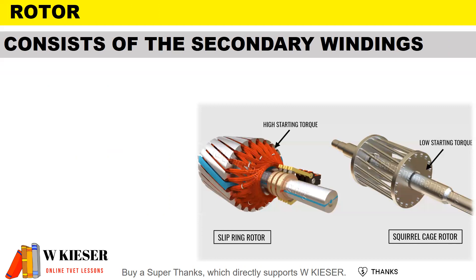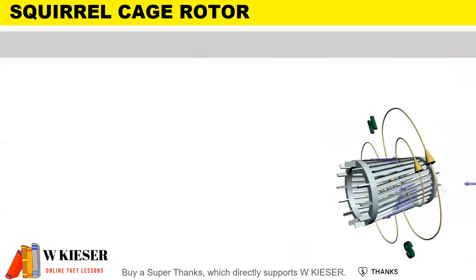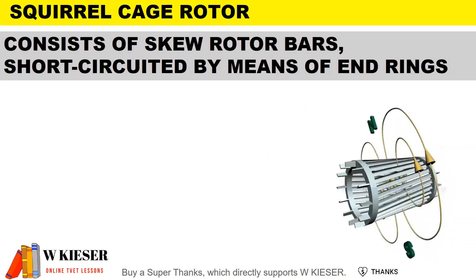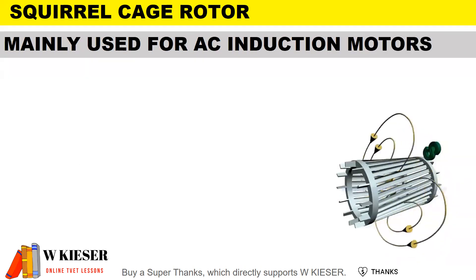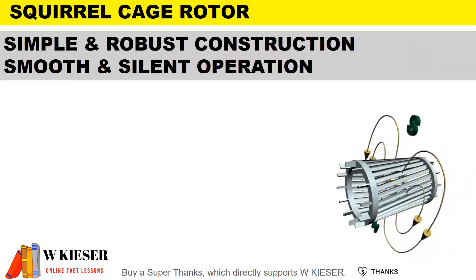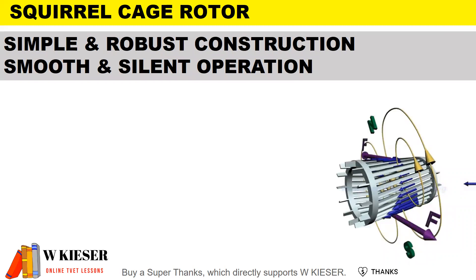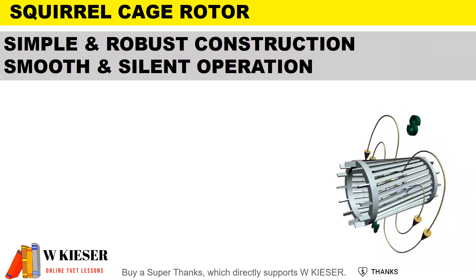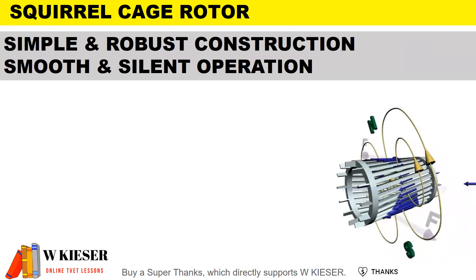For the rotor, it consists of the secondary windings. We have the squirrel cage rotor, which consists of skew rotor bars short-circuited by means of end rings. They are mainly used for AC induction motors. The construction is simple, robust, and strong, with smooth and silent operation, which means it requires very little maintenance.